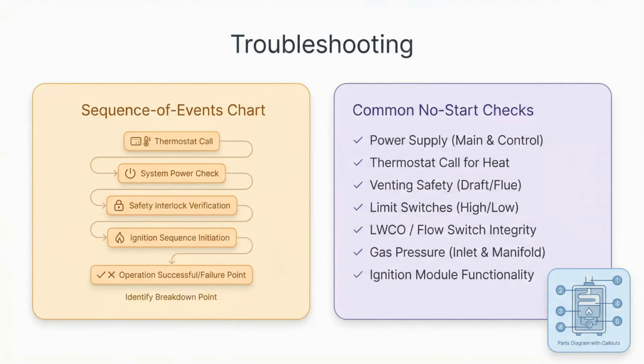Manufacturers usually include troubleshooting built around a sequence of events chart. What should happen, in what order, when there's a call for heat. When a boiler won't start, that sequence helps pinpoint where the chain breaks. And for repairs, the manual's exploded parts drawings and part numbers make ordering the correct replacement much faster.